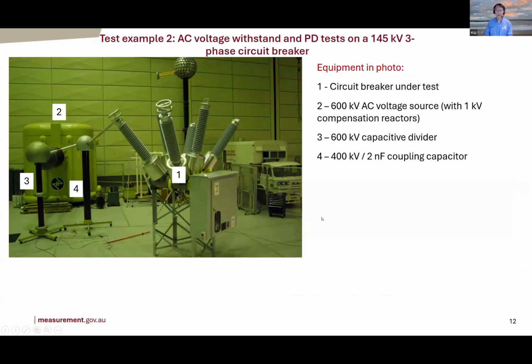Okay, this is another example in the laboratory. Say this is a circuit breaker. You have a bushing, you have some capacitive load, not too much at the moment, but this testing transformer has a compensation reactor that can be set to different settings to compensate the load. By the way, in high voltage testing, the majority of the load is capacitive, and that's why these testing sources always have a reactor as compensation.